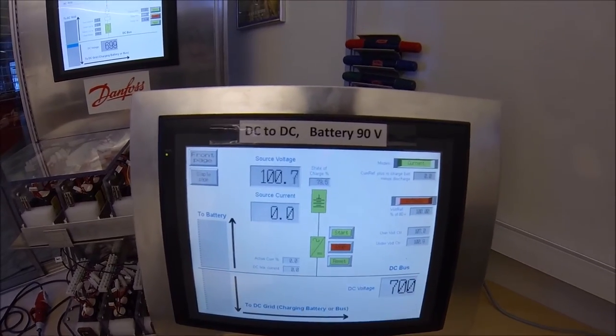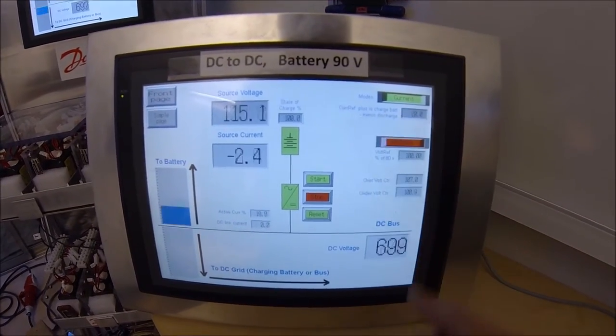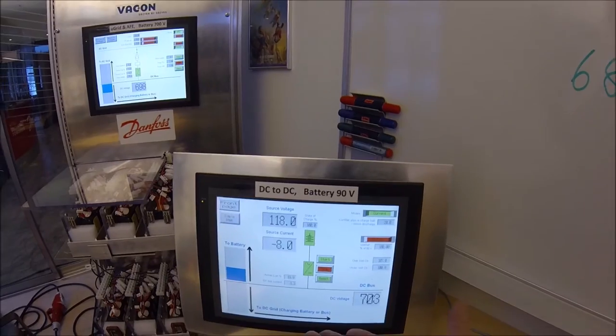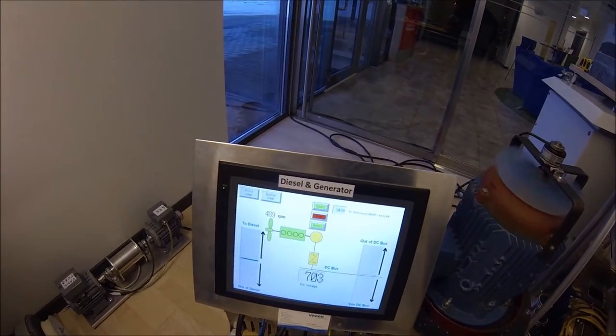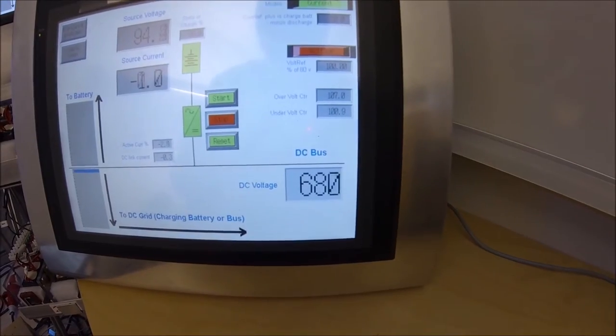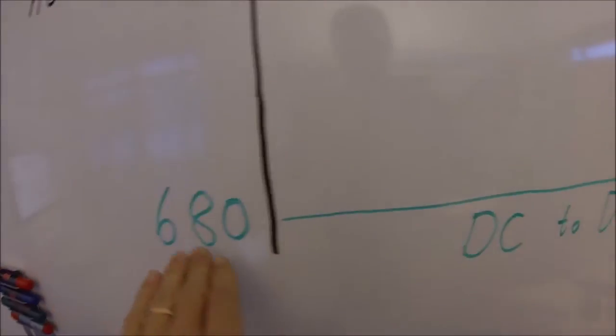The DC-to-DC converter sits here not doing anything. If I want to charge my battery now, I can do that on the DC bus — the energy coming from either of those two sources. Now the energy comes from the generator, and now it comes only from the active front end. If we don't have any energy source, our DC-to-DC converter is set to keep the DC voltage up. The DC voltage now dropped to 680 volts, which is the defined DC-to-DC under voltage controller level for this system with a one percent drooping.